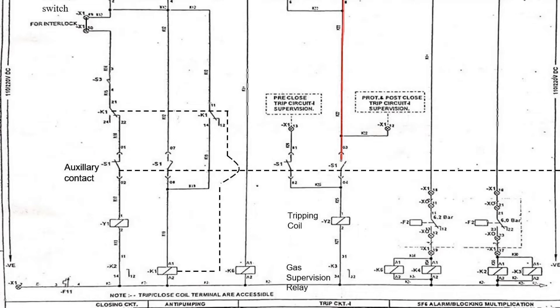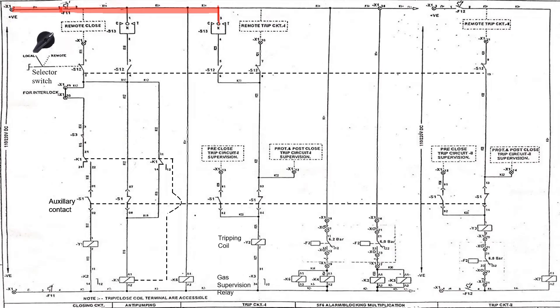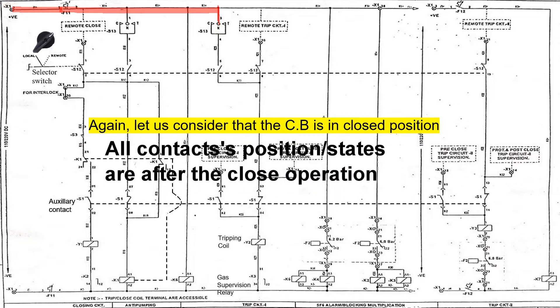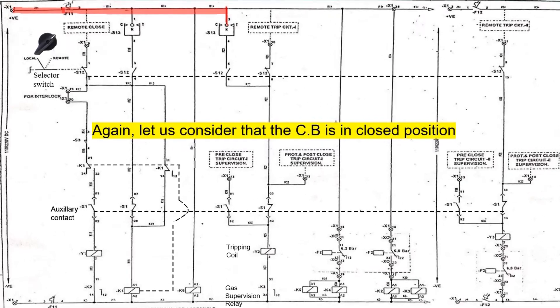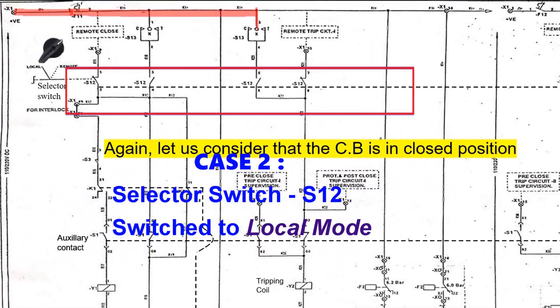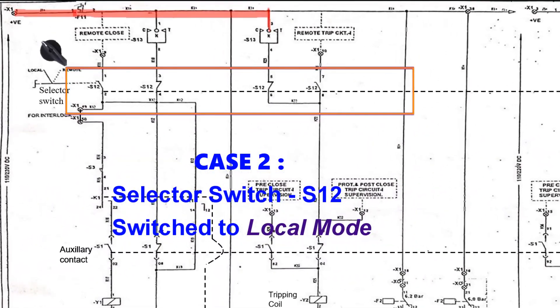Now let us see the tripping circuit in local mode. For open circuit operation in local mode, let us consider that the circuit breaker is in closed position and the contacts shown here are after the circuit breaker closes. In local mode, we previously saw the selector switch S12 connected in remote mode. Now let us consider case 2 where the selector switch is connected in local mode. Then the connection of S12 will be something like this.